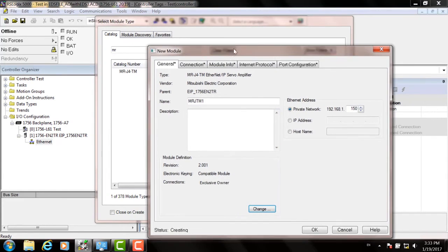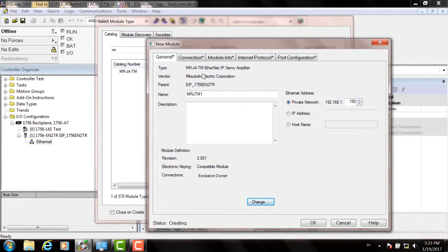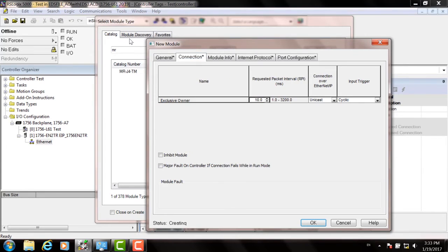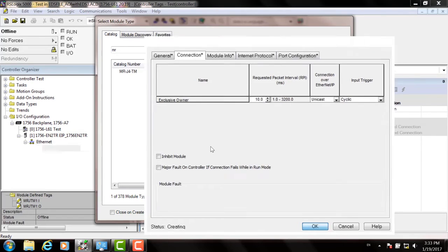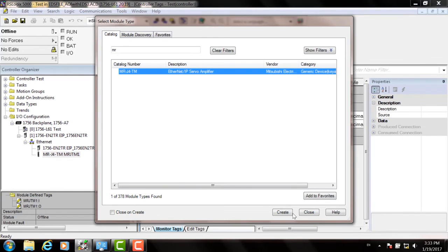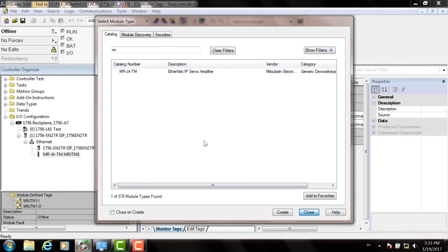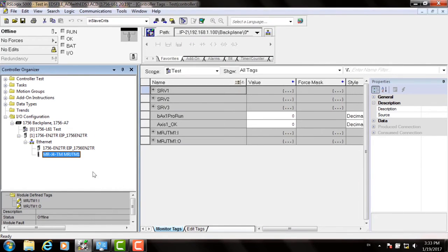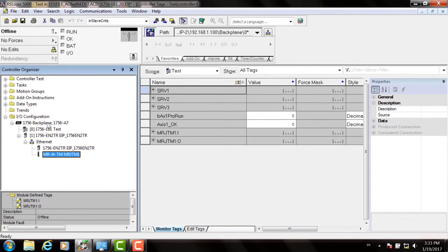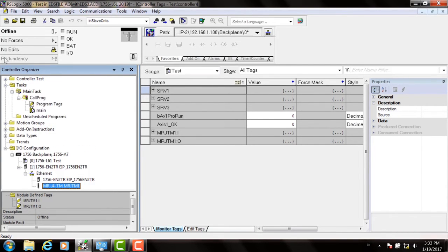Commit the changes with Yes. And now choose the Connection tab at the top. And you can set your RPI or requested packet interval there and click OK. Then hit Close. And your drive now shows up under the Ethernet IP interface it's attached to.